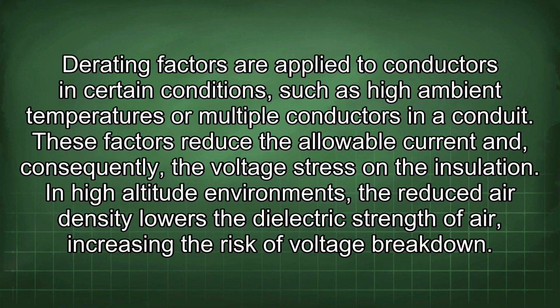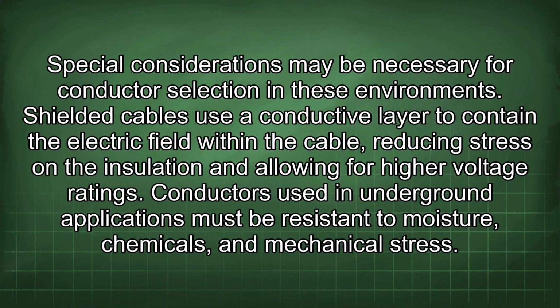These factors reduce the allowable current and, consequently, the voltage stress on the insulation. In high-altitude environments, the reduced air density lowers the dielectric strength of air, increasing the risk of voltage breakdown. Special considerations may be necessary for conductor selection in these environments. Shielded cables use a conductive layer to contain the electric field within the cable, reducing stress on the insulation and allowing for higher voltage ratings.